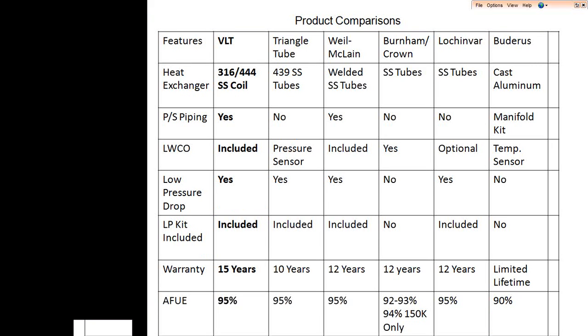So this is a little product comparison between ourselves and the other competitors and manufacturers of high-efficiency equipment: Triangle Tube, Weil-McLain, Burnham and Crown, which is the same company, Lochinvar, Buderus. And you'll see that, again, we have the most robust heat exchanger, domestically manufactured of 316 stainless with the 444 fins. We're one of the few manufacturers that include the primary secondary piping. We do include a low water cutoff. A couple other manufacturers use temperature or pressure switches. And the fact that we have a low pressure drop.